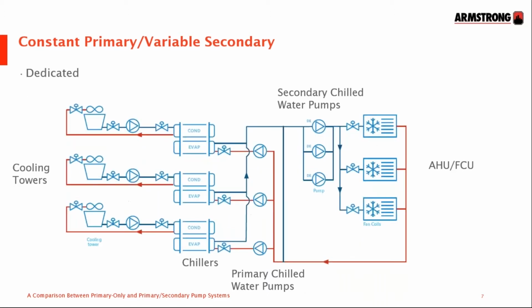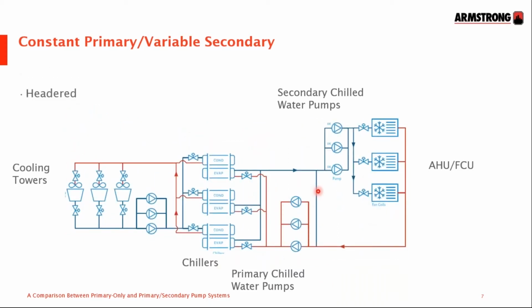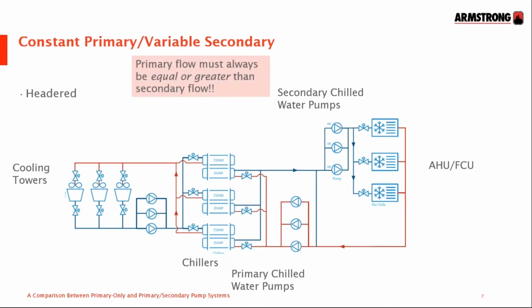The previous slide here showed dedicated pumps for the chillers. They're often used if you have different sized chillers so that you can have pumps sized to match each chiller so that you get the right flow through each chiller all the time. The alternative is to have headered pumps. Those work best with identical sized chillers, and the benefit here is you have greater redundancy because any one pump can handle any of these three chillers shown here.